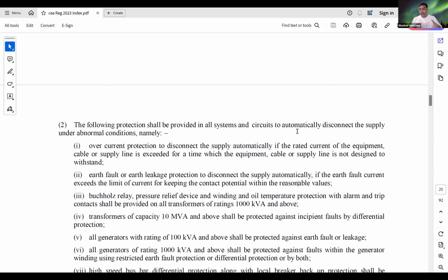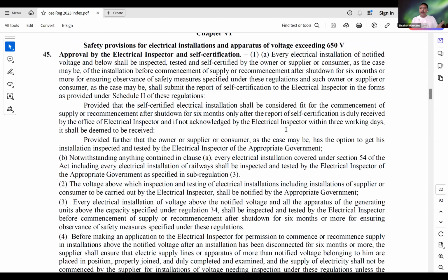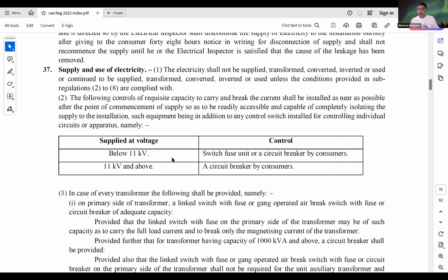So the circuit breaker at the consumer's premises was introduced. If you read this regulation properly, there are two things, primary side and secondary side. We want isolation at different stages, and it should be done conveniently in the shortest time. That's why this distinction of above and below 11 kV and the circuit breaker point was introduced. That is my take. After this introduction, Maharashtra has started implementing air break switches or gang operated switches before the consumer's premises at the 11 kV level, which was not there earlier in Maharashtra. Thank you. That is the point I want to highlight.